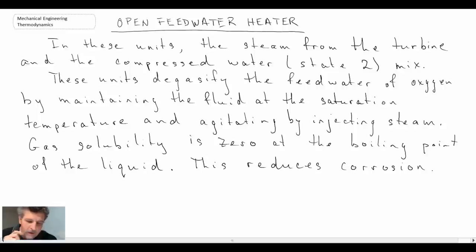So with the open feed water heater what we're doing is we're taking steam from the turbine and we're mixing that with the compressed water at state two and the mixture is coming together. Another thing that the open feed water heater does is it helps degasify the feed water.